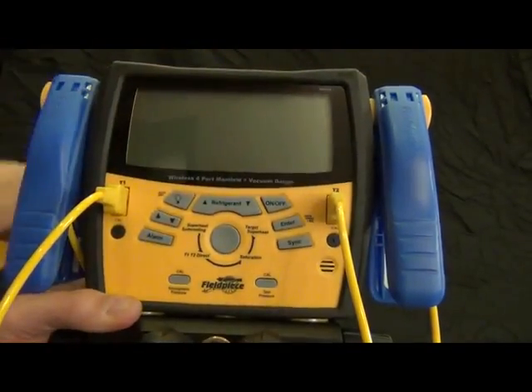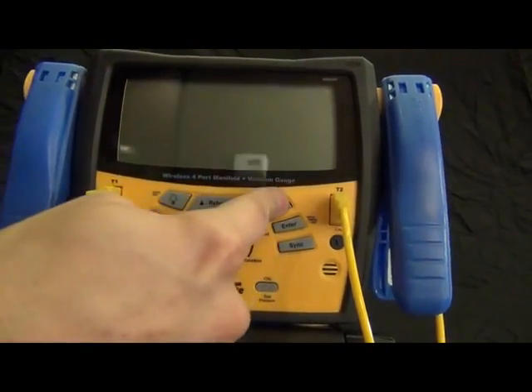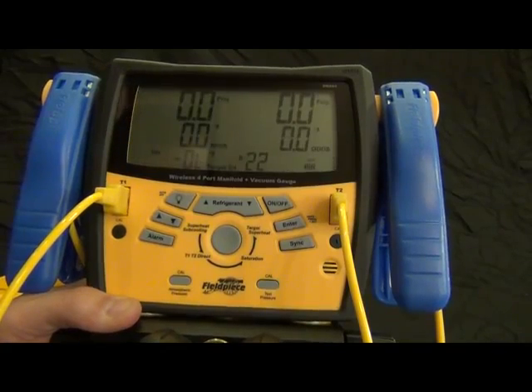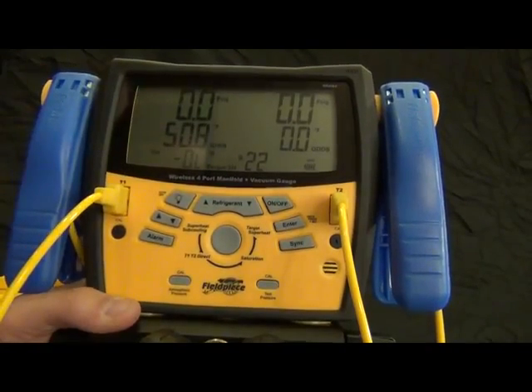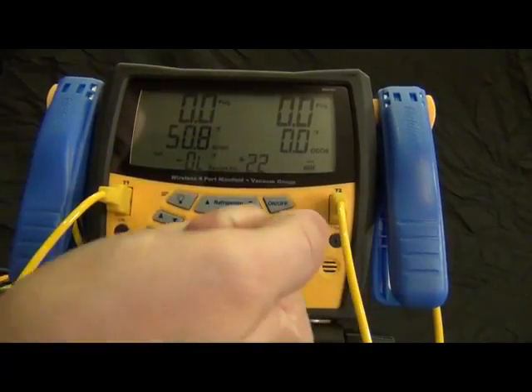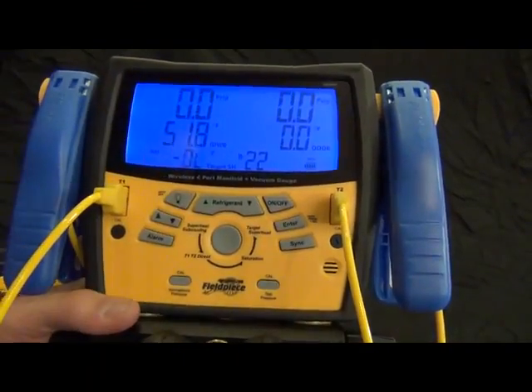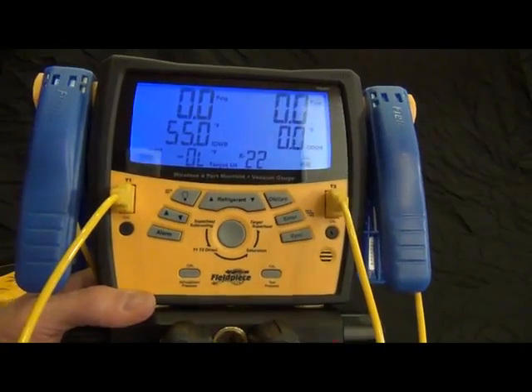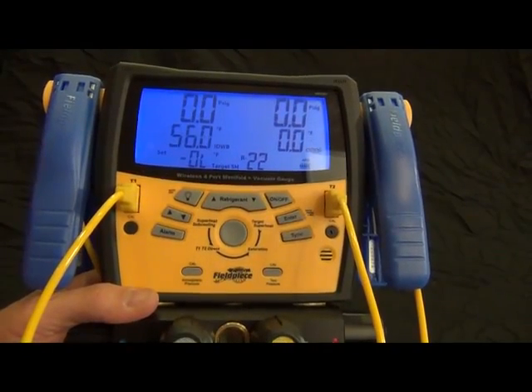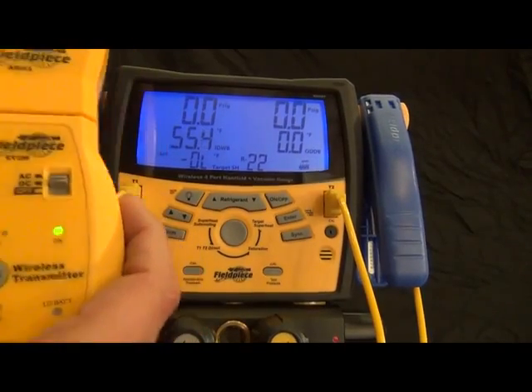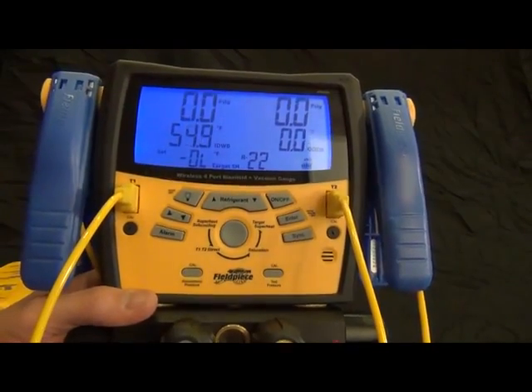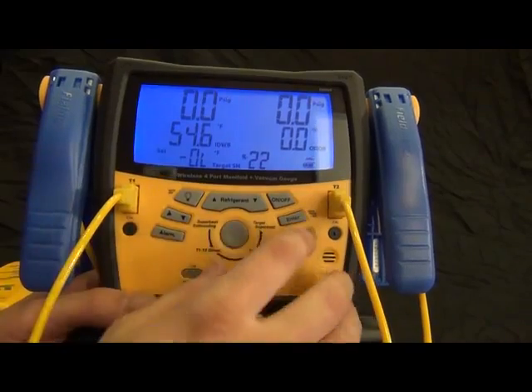Now what's cool about it is you saw that 50 degree before. If you sync it once, it actually remembers. So I can go ahead and turn this off. Turn my ET2W off. And then when I go ahead and turn it back on, it'll remember that wet bulb. So you can see that's a live measurement that I have right there just by turning it on and off. So once you do it once, it's actually really easy as long as you keep your wet bulb accessory head, the ARH-5 onto this particular ET2W, then it'll always get synced up right here. So it makes it real easy for setup after the first time.